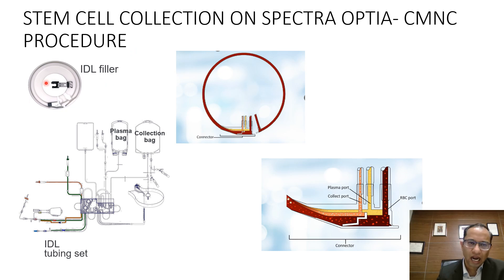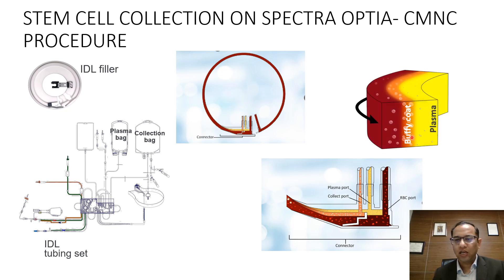Stem cell collection on Spectra Optia is run through an IDL filler and it also has an IDL tubing set. Blood enters from the inlet line into the centrifuge, goes into the connector, and there is a soft spin forming three layers: the red cell layer, the buffy coat layer, and the plasma layer — which is platelet-rich plasma. Once those layers are formed in the connector, different ports are used for different collections. The middle layer containing WBCs and CMNC is collected from the collection port, while plasma and red cells return to the patient.